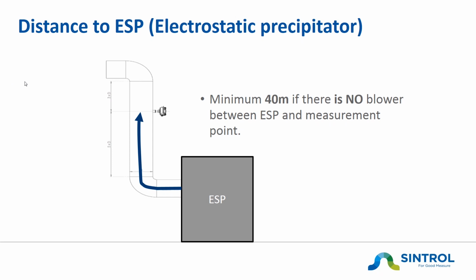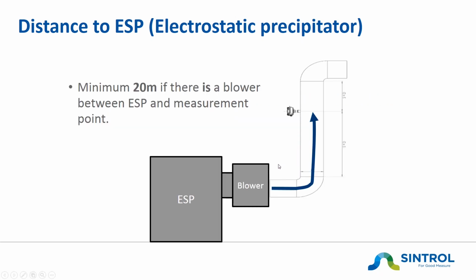Distance to the electrostatic precipitator. If you are measuring with our instruments after an ESP, you should note that each ESP will create an electrostatic field which may have an influence to our measurement. That field will disappear over the distance. Now, if you have just only one or two bends in between ESP and our measurement, please make sure that you keep a minimum of about 40 meters. If you have a blower in between ESP and our measurement point, that distance decreases a lot to about 20 meters. After that, the electrostatic or electromagnetic field of the ESP will be disappeared.